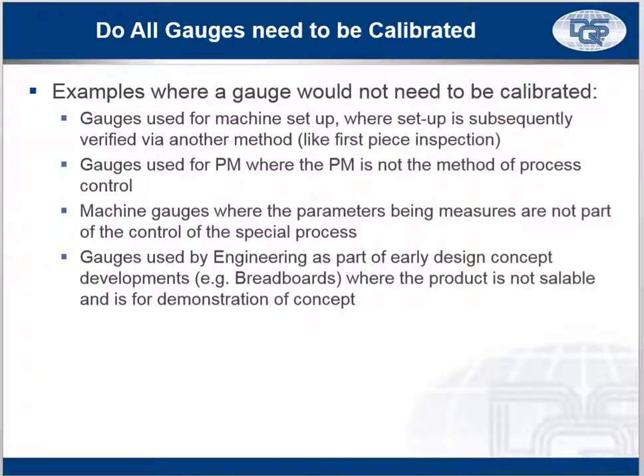Okay, examples where a gauge would not need to be calibrated. A lot of times if you're observing a setup, you'll see them using gauges to measure certain things. They're doing that to make sure the setup is correct, so it cuts down on their time. But the real control of that process may be done through something like a first piece inspection. So therefore, those gauges used in the setup would not need to be controlled. Gauges used for preventive maintenance might not need to be controlled. Machine gauges where parameters, we just talked about this, the special processes, I gave you an example. And gauges used by engineering as part of early design concepts like the building of breadboards, where they're not selling the product, they're just using it for demonstration concept. Those might not need to be calibrated.